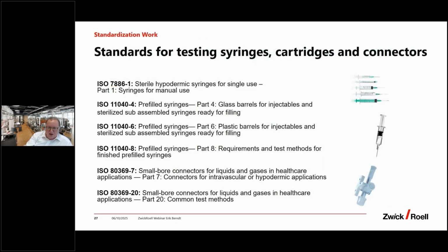So I've spoken now on the needle-based injection systems, but for sure here we have integrated prefilled syringes in an autoinjector. We have cartridges in the pen systems, and this means we also have to look at further standards. And these here are the standards perhaps which are for syringes, also for the single use, the prefilled ones, and the connector ones. The first standards were recently updated, and more are following as we are trying to align these standards with the required testing procedures.